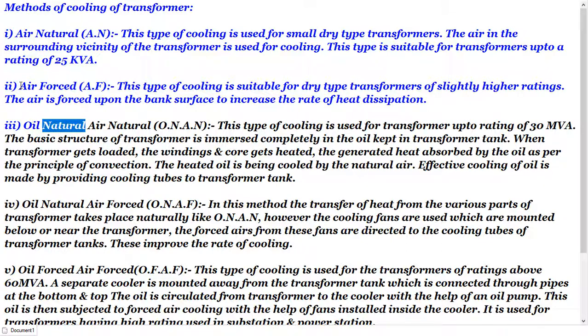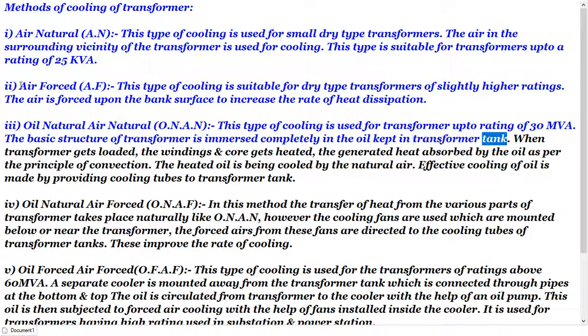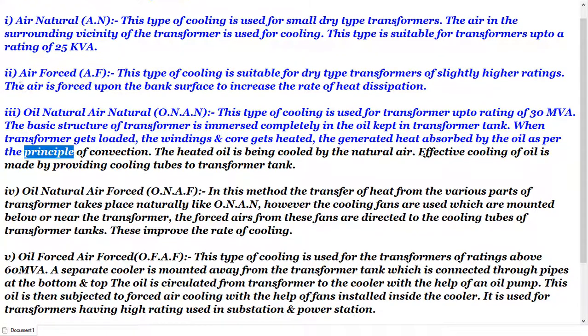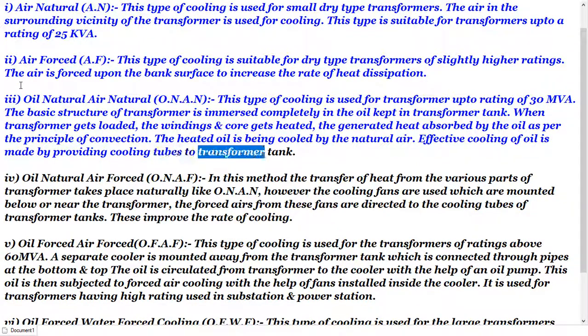3. Oil Natural Air Natural (ONAN): This type of cooling is used for transformers up to a rating of 30 MVA. The basic structure of the transformer is immersed completely in oil kept in the transformer tank. When the transformer gets loaded, the windings and core get heated. The generated heat is absorbed by the oil as per the principle of convection. The heated oil is then cooled by natural air, and effective cooling is made by providing cooling tubes to the transformer tank.